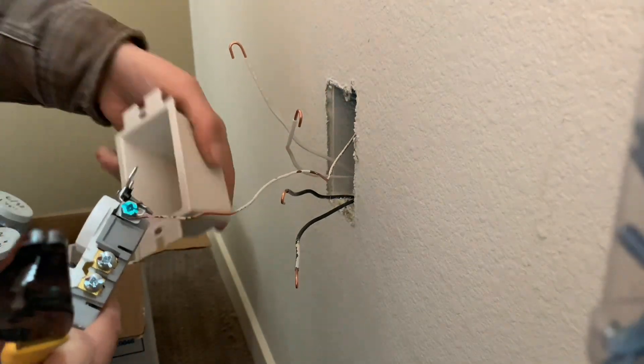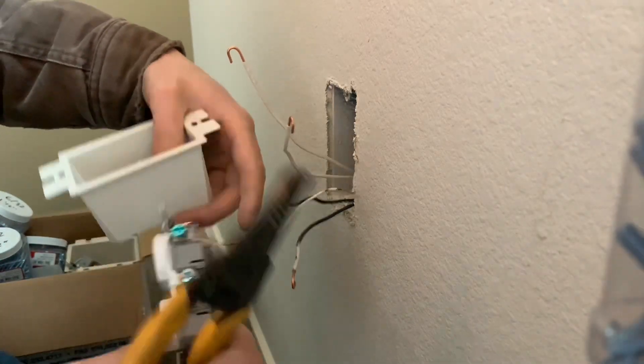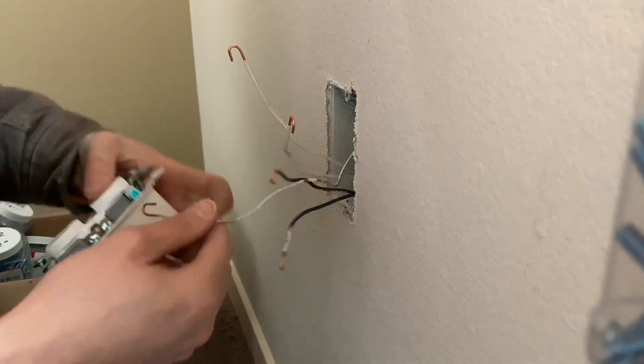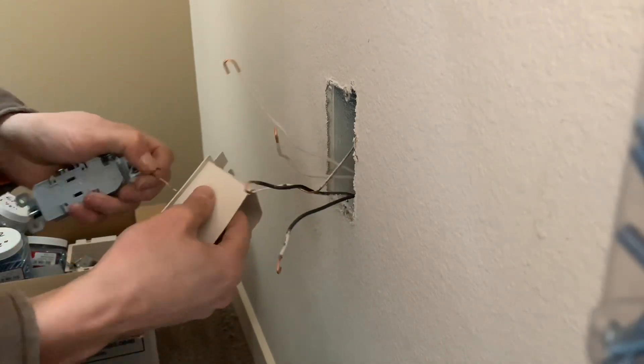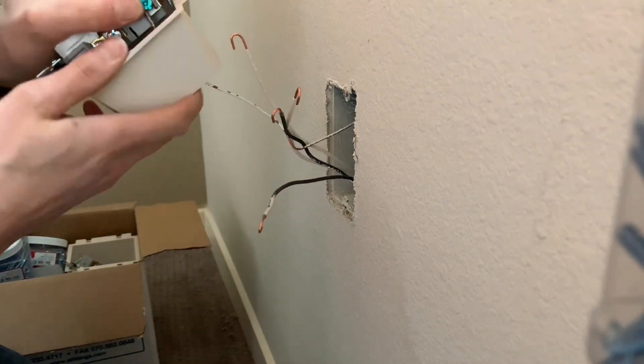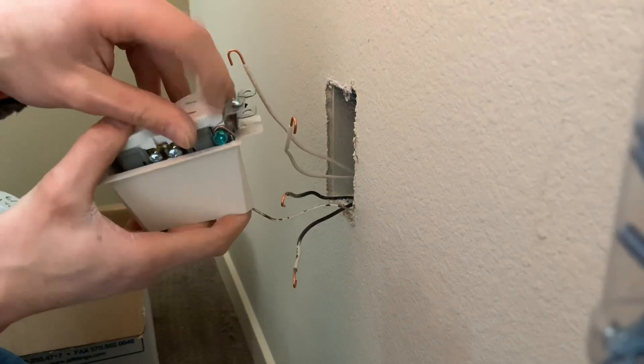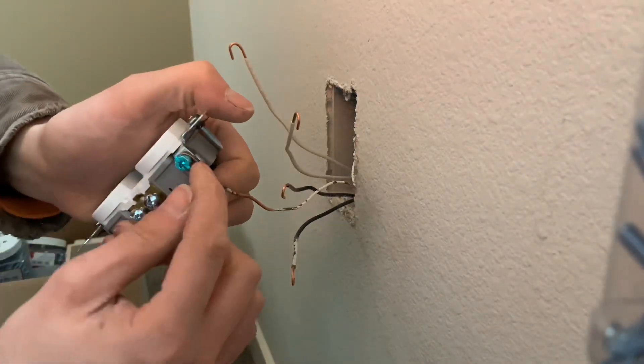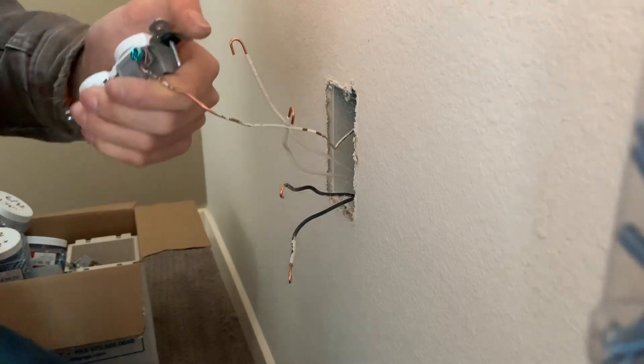And if you have to use a box extension, it's a nightmare to shove it through when the wire is sticking out. If the wire is sticking out like this and you try to push it through the plastic extension, it catches on the edge. So for everyone's sake, keep it inside — there's a little marker. You can fold the loop in on itself and tighten it for a better connection.